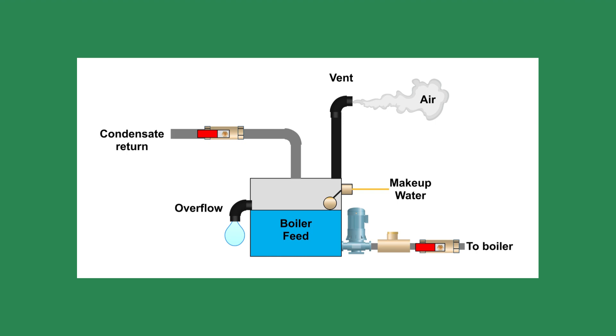It is like a steam system. When the boiler is off, the piping is filled with air. Once the boiler starts generating steam, the steam will push the air through the piping, vented through the condensate piping, and out the boiler feed or condensate unit vent pipe. Sags in the piping create a water seal that can stop the air and steam from venting. Ask yourself this simple question: if I were air, how would I escape?